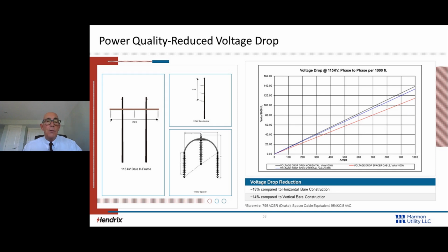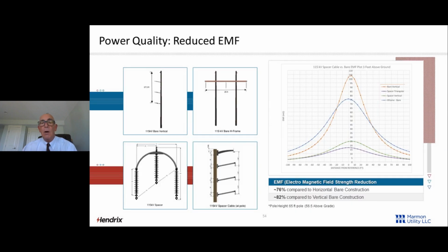Power quality, reduced voltage drop. We know we've got 15 to 20% reduced impedance, 15 to 20% better voltage regulation, buying less aluminum, better end-of-line voltage. Fantastic. We know that because we're canceling out the EMF, we've got 76% less EMF compared to bare and 82% less EMF compared to vertical construction.